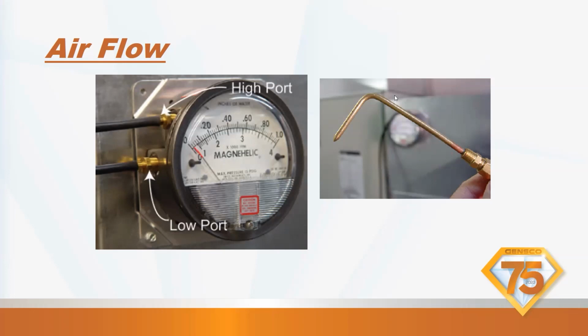You can almost see the little dots. It looks like pepper on the angled part of that probe. That's how you know that we're measuring the static pressure of the duct and not the velocity pressure. The velocity pressure would have a hole on the end of that probe that allows the velocity to be measured, okay? We don't want the velocity, we just want the static pressure. That's what we're looking at.